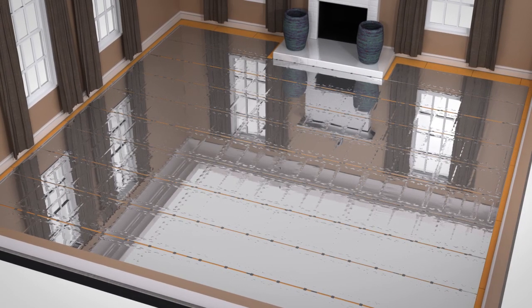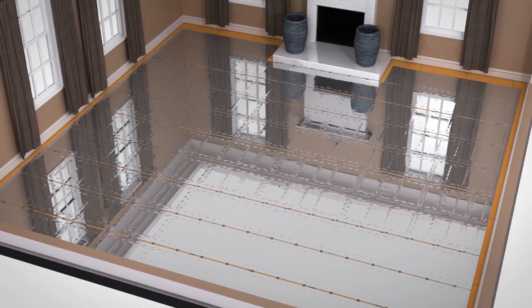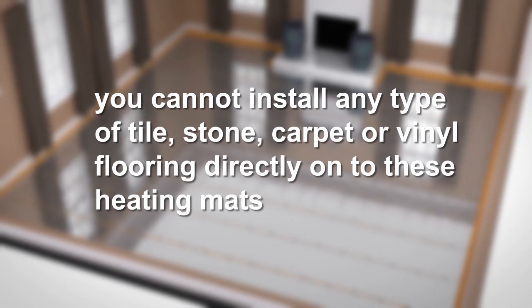Underfloor heating systems are designed to sit directly on top of insulation and directly below laminate or suitable engineered or solid wood floors. Please note you cannot install any type of tile, stone, carpet or vinyl flooring directly onto these heating mats. They are specifically designed to be used with floated wooden floors. This means you cannot use any tile adhesives, levelling compounds or wood glues of any kind. Always make sure the floor coverings are suitable for use with underfloor heating.